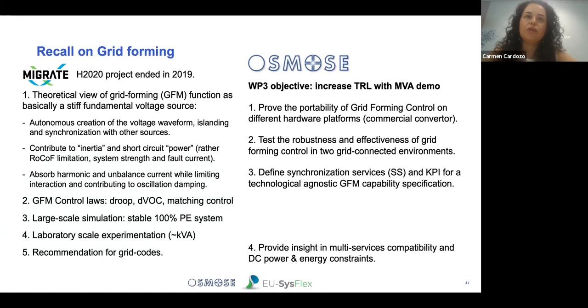The project Migrate, which ended 2 years ago, proposed a theoretical view on grid forming - basically a way of describing the behavior of a VSC converter as a stiff voltage source. This entails capabilities such as autonomous creation of a voltage waveform, the capability of islanding, and mainly synchronization with other sources. This usually brings the capability to contribute to inertia and short circuit power, but these terms can be confusing when talking about converters, so sometimes we prefer to talk about ROCOF limitation and system strength, separating this from fault current injection.